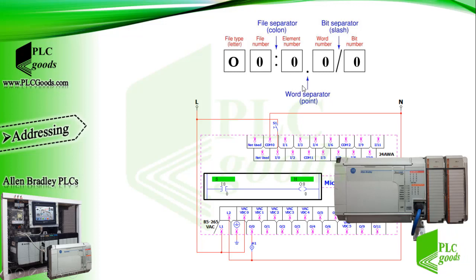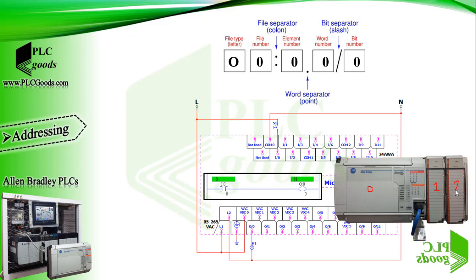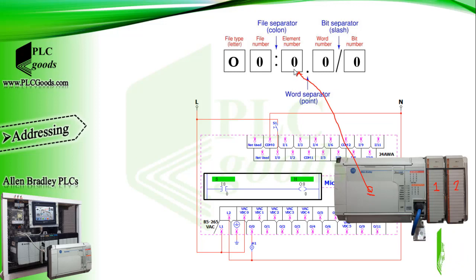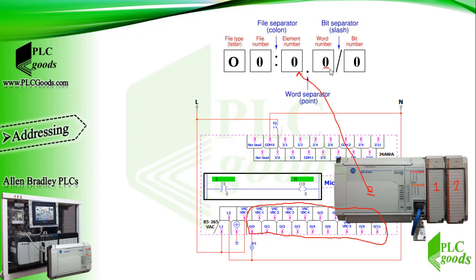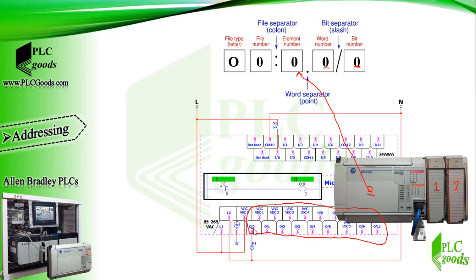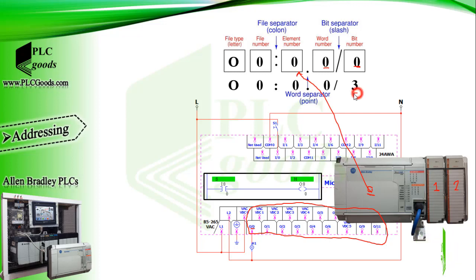The letter O indicates the address is for a PLC output. The file number is 0 and can be omitted. The colon is a separator. The next number indicates the element or slot number holding the actual output, which can range from slot 0 to a maximum of 30. My system has three modules with slot numbers 0, 1, and 2. The next number indicates the word number — a word has 16 bits, and my CPU has 12 digital outputs so one word stores all output statuses. After the forward slash, the bit number or terminal number is determined. In Micrologix 1500 with 12 output terminals, 0 means terminal O0 and 3 refers to terminal O3.